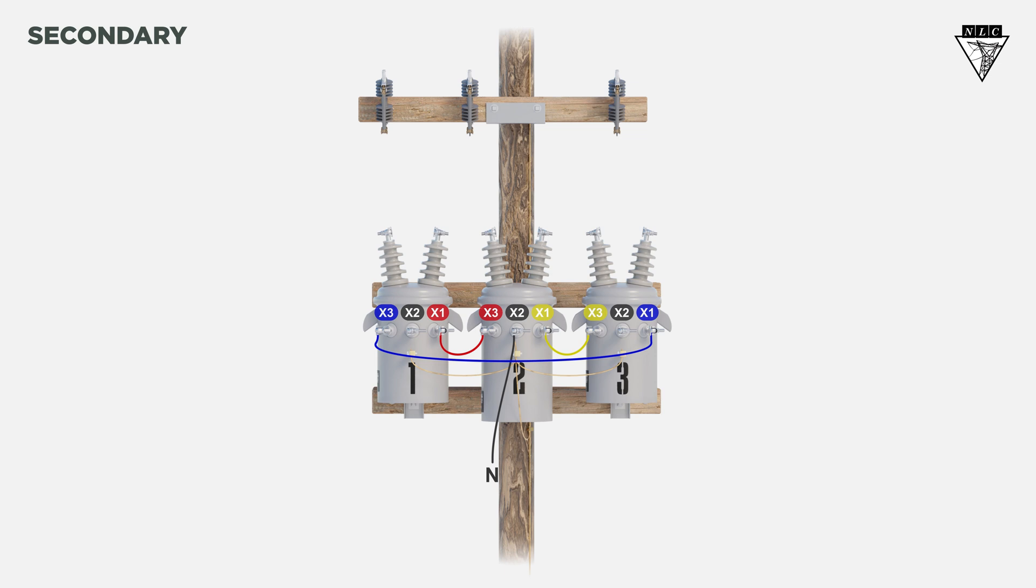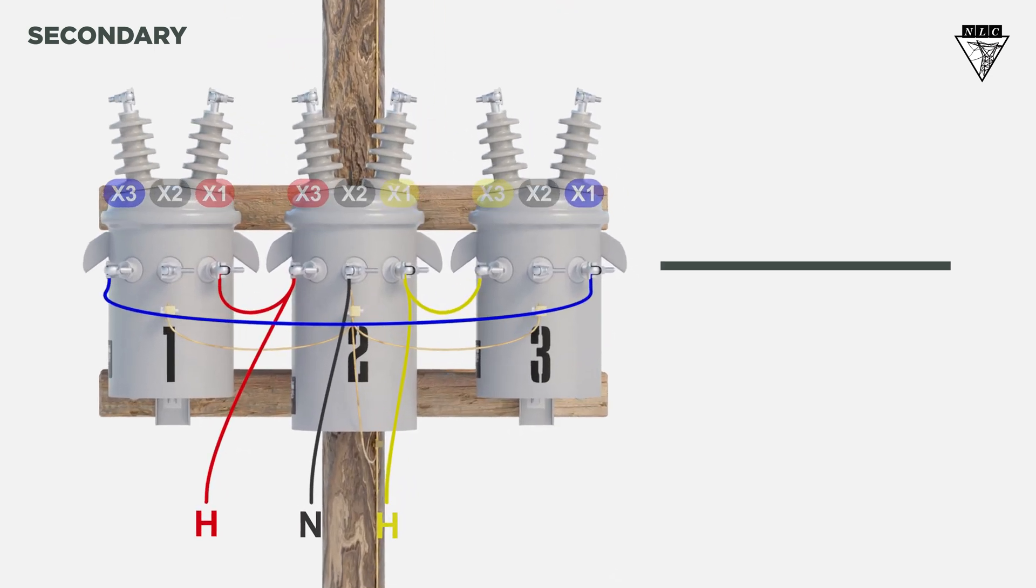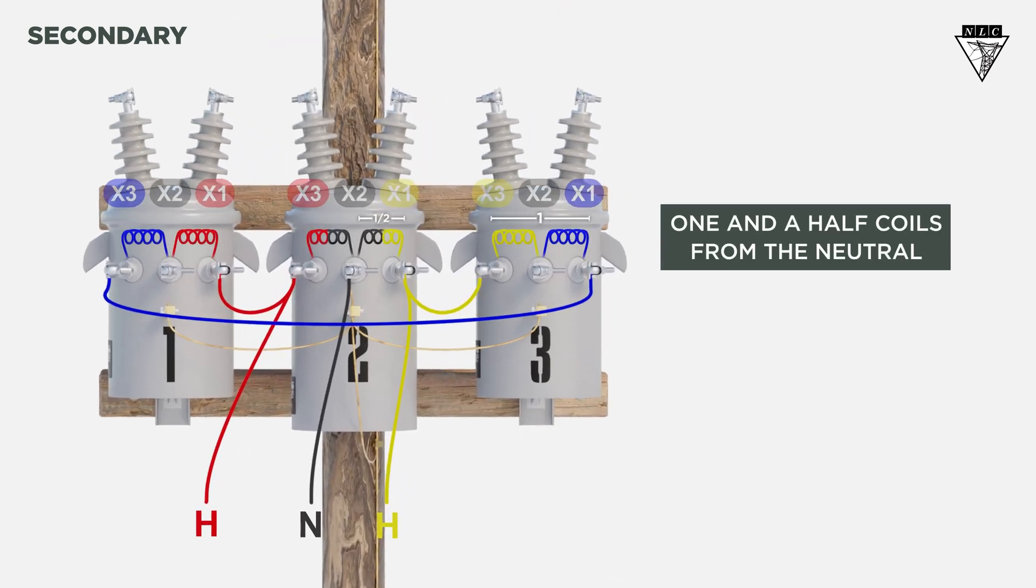Run the hot legs from the X3 and X1 of the lighting transformer. Finally, place the power leg one and a half coils from the neutral. For this example, we'll use the X1 bushing on the third transformer. This is now our power transformer.